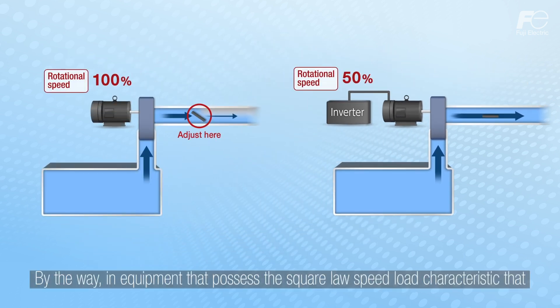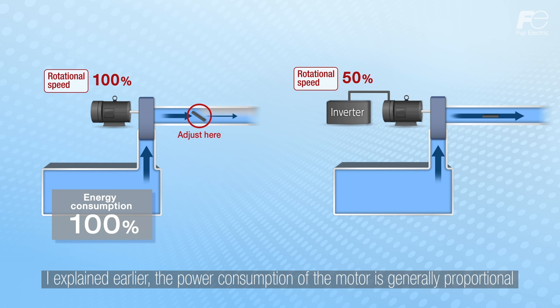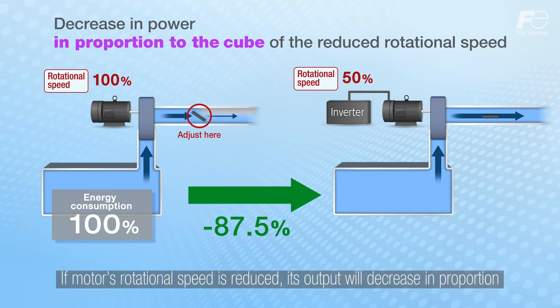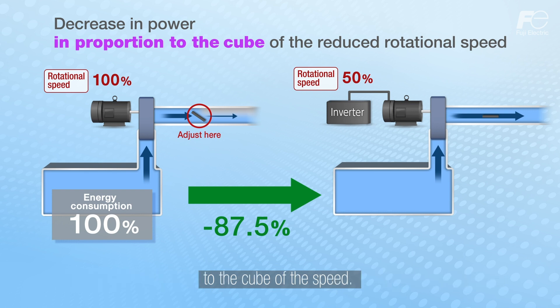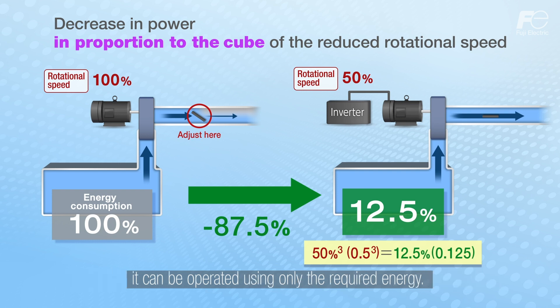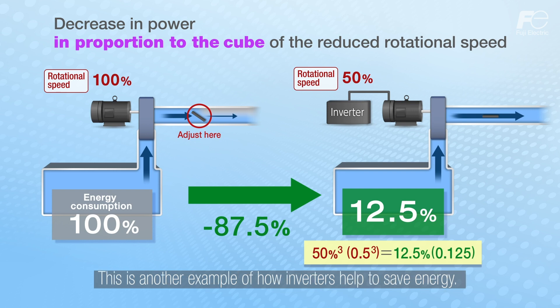In equipment that possesses the square law speed-load characteristic, the power consumption of the motor is generally proportional to the cube of the motor's rotational speed. If the motor's rotational speed is reduced, its output will decrease in proportion to the cube of the speed. If the pump is operated at a rotational speed consistent with the flow rate, it can be operated using only the required energy. This is another example of how inverters help to save energy.